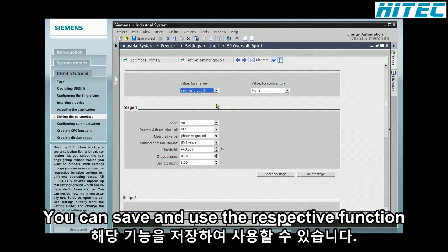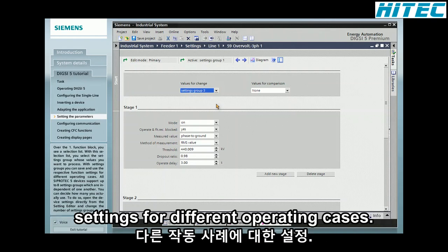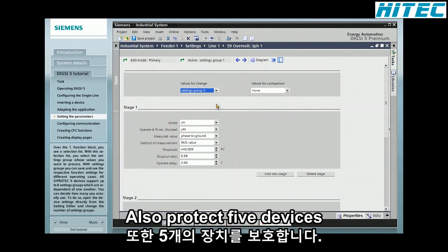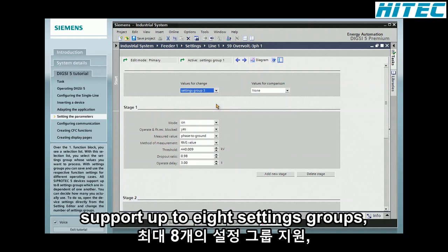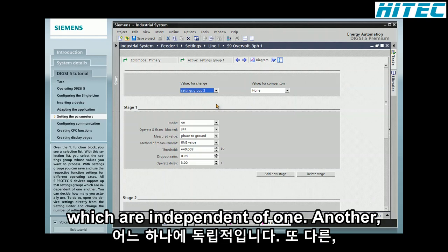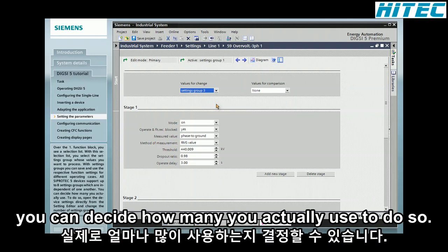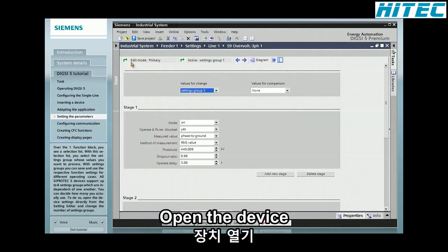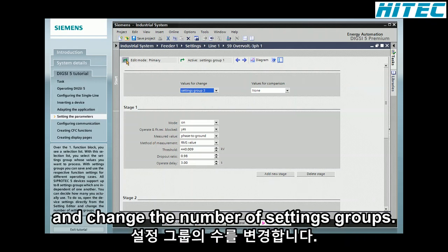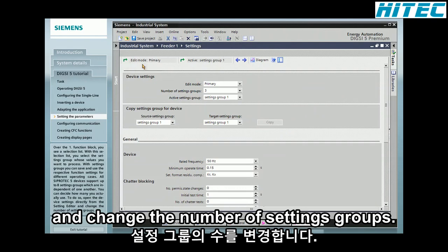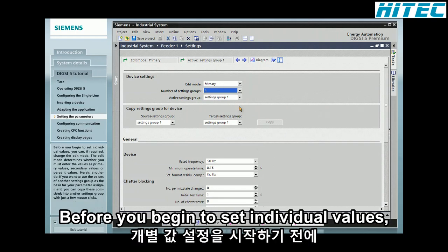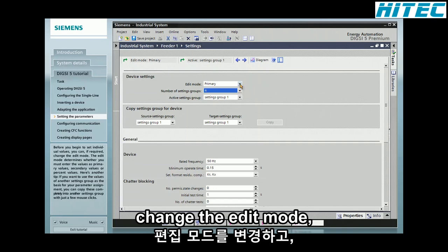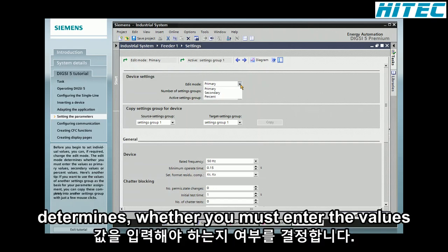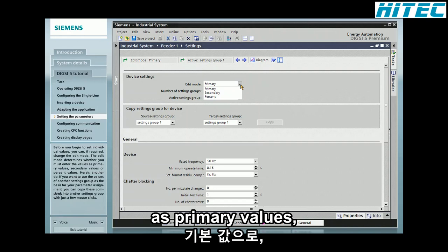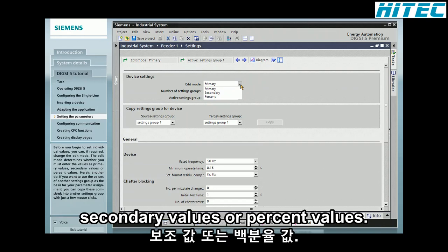With settings groups, you can save and use the respective function settings for different operating cases. All SIPROTEC 5 devices support up to 8 settings groups, which are independent of one another. You can decide how many you actually use. To do so, open the device settings directly from the setting editor and change the number of settings groups. Before you begin to set individual values, you can, if required, change the edit mode. The edit mode determines whether you must enter the values as primary values, secondary values, or percent values.